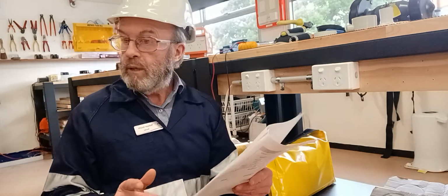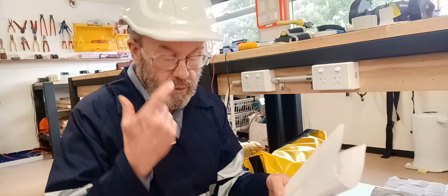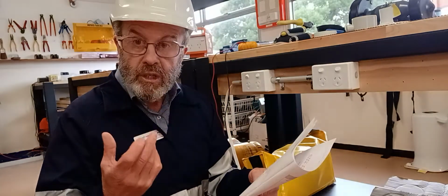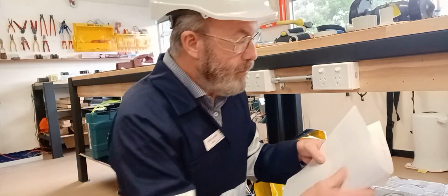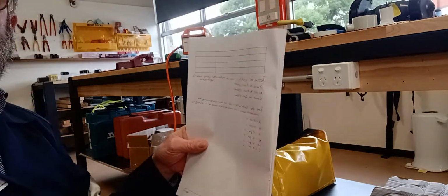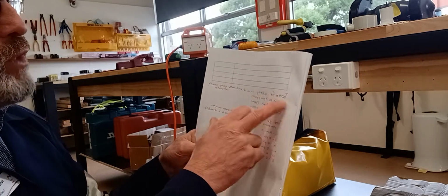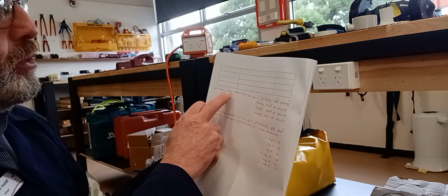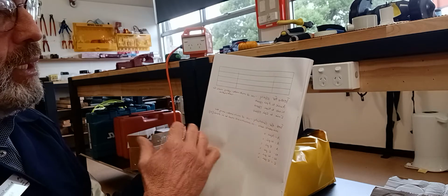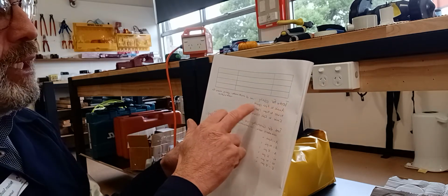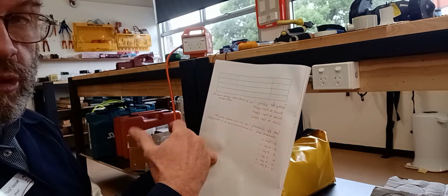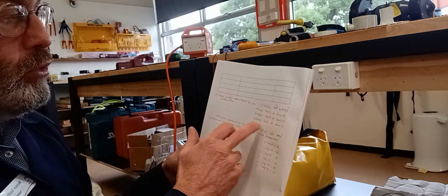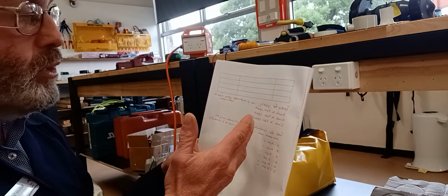I would like you to use one of the multimeters that has a little noise associated with it when we have a closed circuit. Now, we have 2 different types of tests, and I'd like you to detail the tests in this sort of format. So you can see there, the test for polarity, we're using a multimeter, using the noise for confirmation. Our tests will be the active to the active pin, which will get a noise, the neutral to the neutral pin, which should get a noise, and the earth to the earth pin, and we should get a noise.